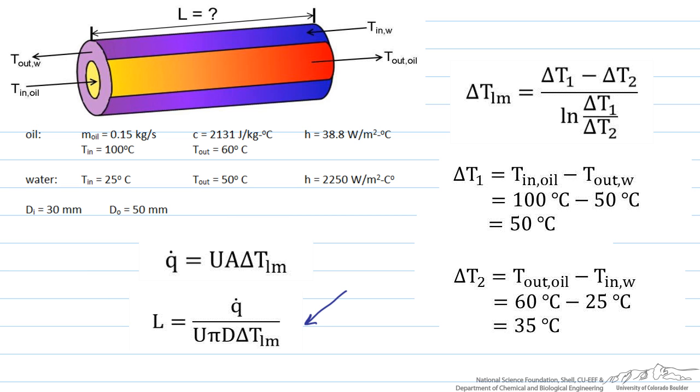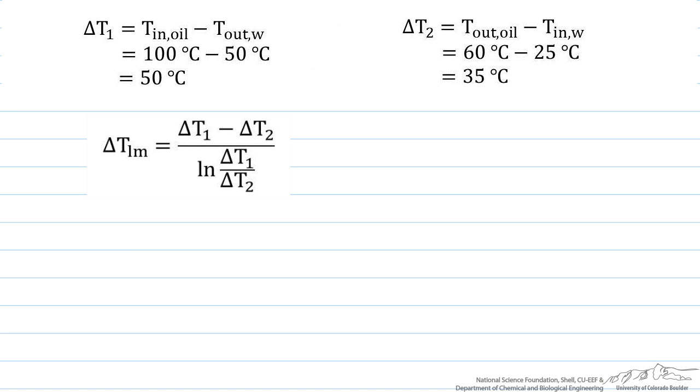Now let's find delta T log mean using these values. This is going to be delta T1, which is 50 degrees C, minus delta T2, which is 35 degrees C, all divided by the natural log of 50 degrees C divided by 35 degrees C. And when we calculate this, we find that our delta T log mean is equal to 42 degrees Celsius.